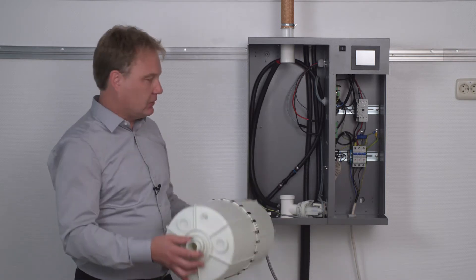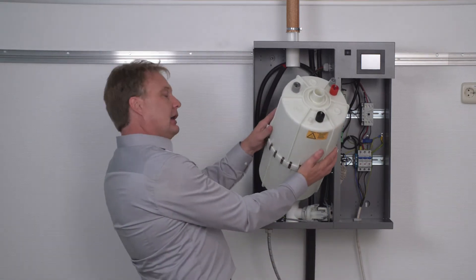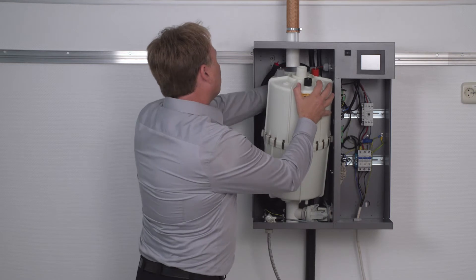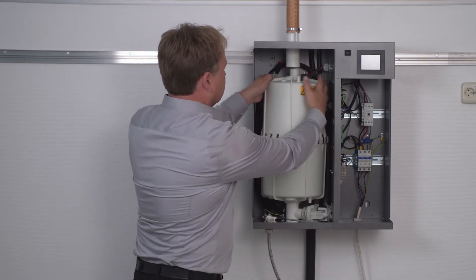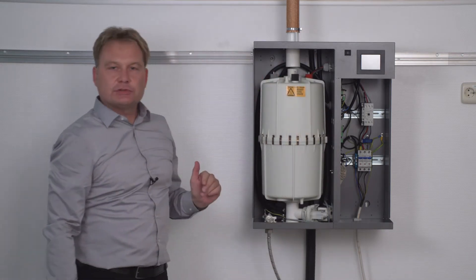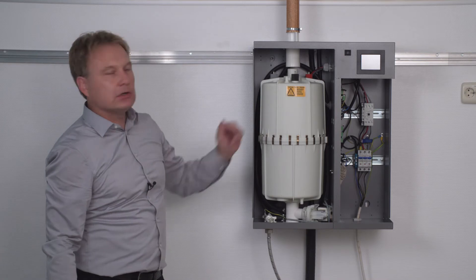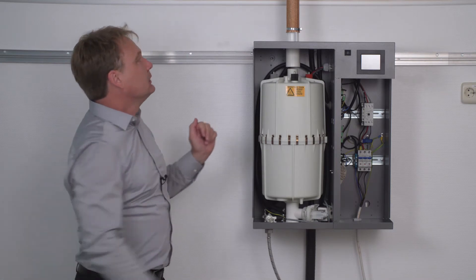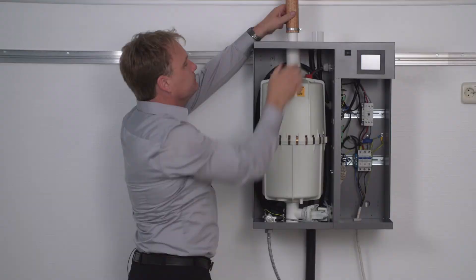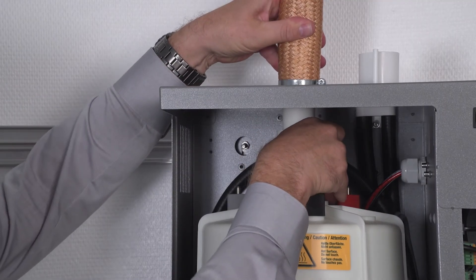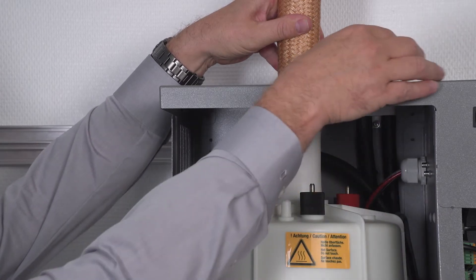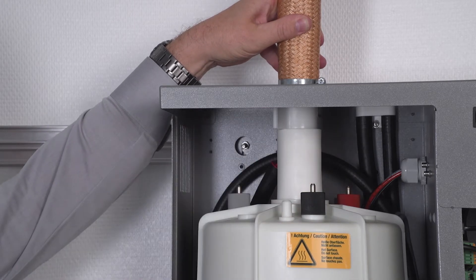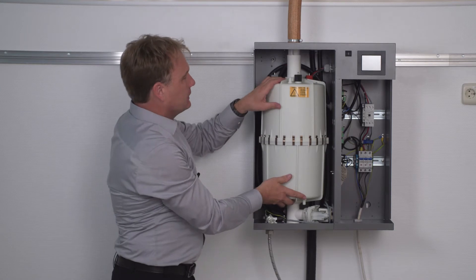After I've cleaned the steam cylinder, I can begin reinstalling it. Simply insert the steam cylinder into the cylinder base. Press down and position it here. The correct position of the cylinder is when you can see the sign, caution hot surface. To affix the steam cylinder, I remove the clip from the steam hose adapter and attach it to the steam cylinder. Now I can take this clip and reaffix the steam hose adapter. The whole steam cylinder is nicely attached.